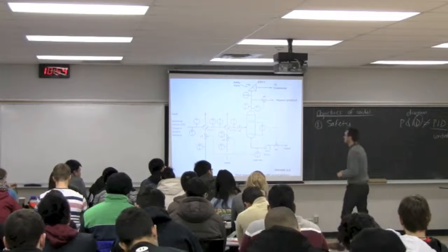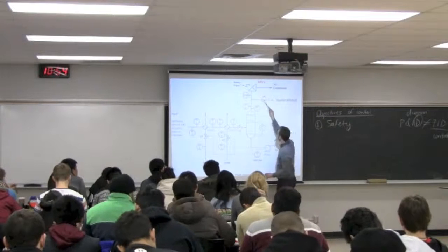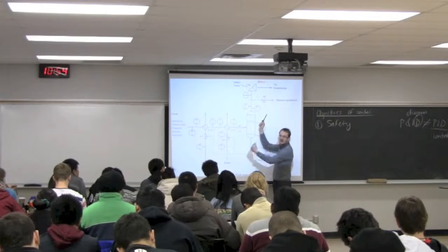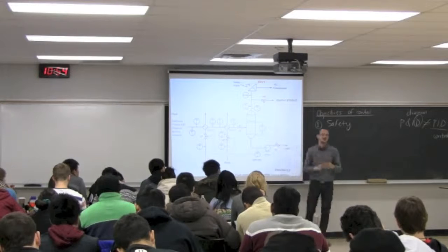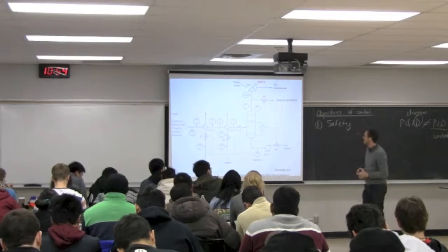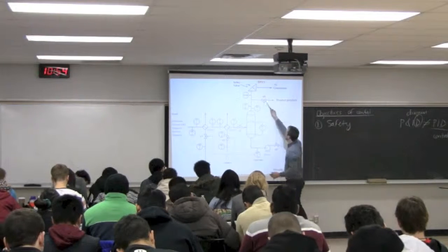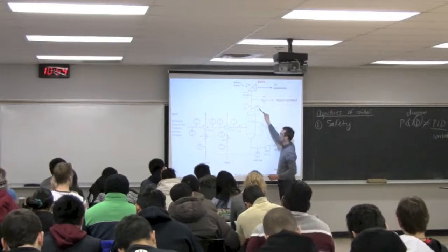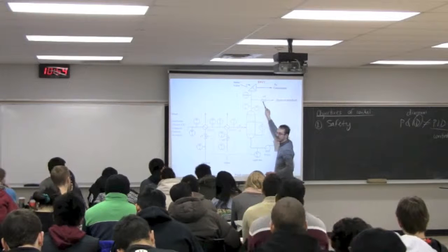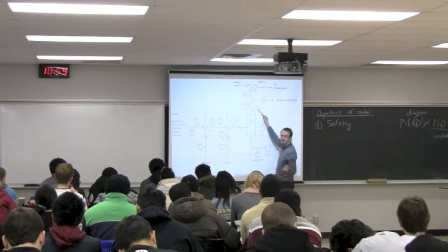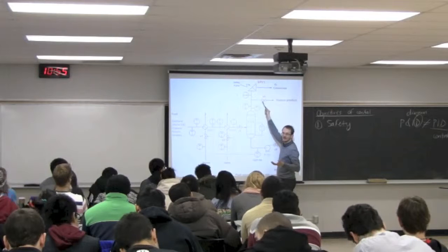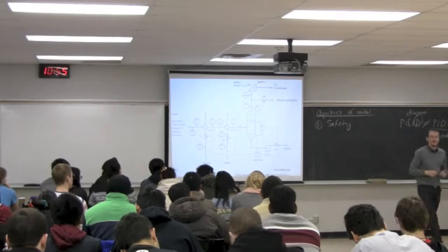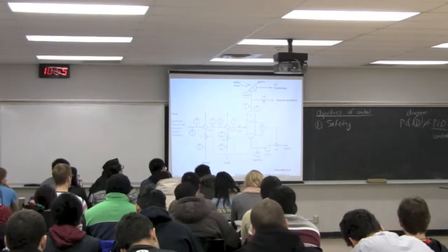Okay. So, for example, if all these valves, V4 and V5, are closed, V3 is open, and you keep pumping material in here, there's a limit to the capacity that that vessel can take. So we have V4 on a control loop with PC1. P, pressure. C, controller. We're manipulating that valve position in an obvious way. Pressure goes up, valve opens. Okay? So that loop is primarily for safety. PC1 is for safety.